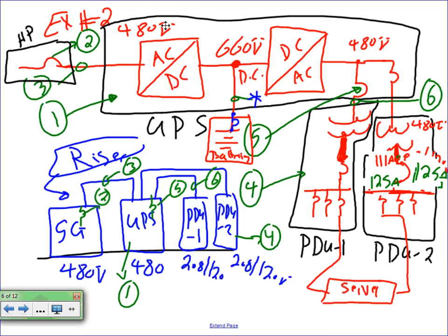So that server, imagine, guys, a laptop with 2 outlets like this. That's basically a laptop with 2 outlets, both tied to different sources. So that's what you're looking at. You have an outlet coming from circuit number 1 here and here, PDU1, PDU2. The 2 PDUs are tied to 2 different UPS systems most of the time. In our case, we're tying them to the same UPS system, and then the whole system is fed from a panel.